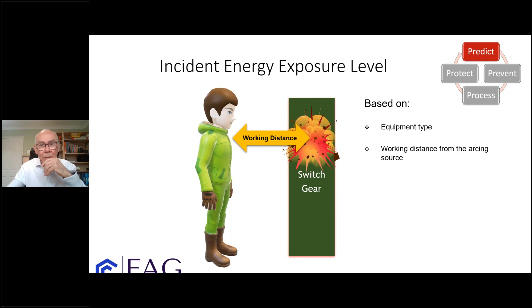Next is the arc flash boundary. It gives the information about the arc flash boundary, and this is the distance from a prospective short circuit current where the incident energy is calculated to drop to this magic figure that I talked about before, 1.2 calories per square centimetre, a bit like holding a match on your skin for a second. That's the sort of heat we're talking about. It hurts, but it will recover. It's likely to be a partial thickness burn at worst.